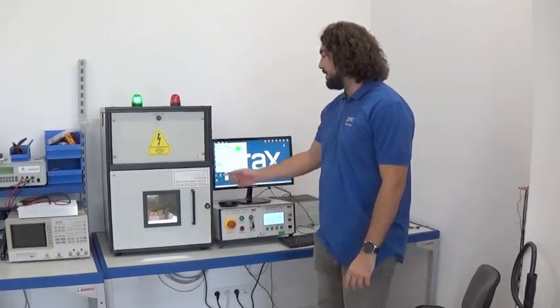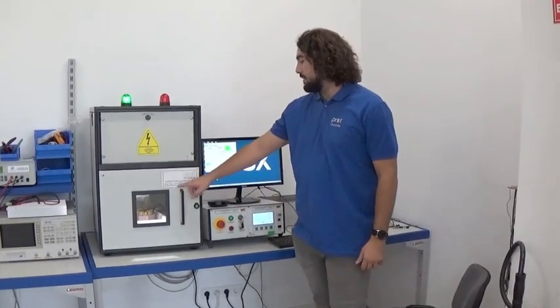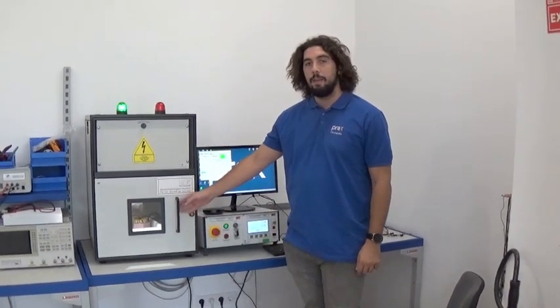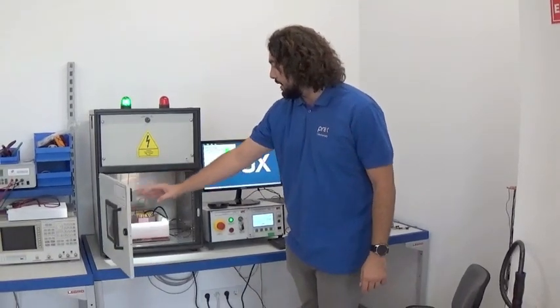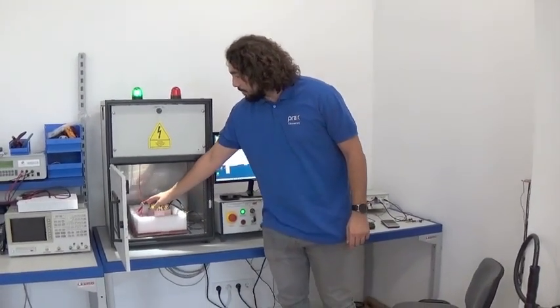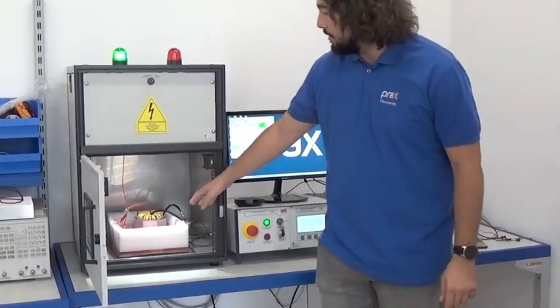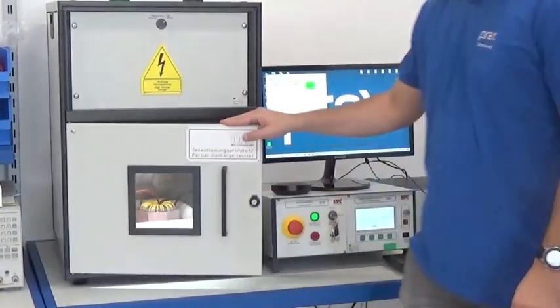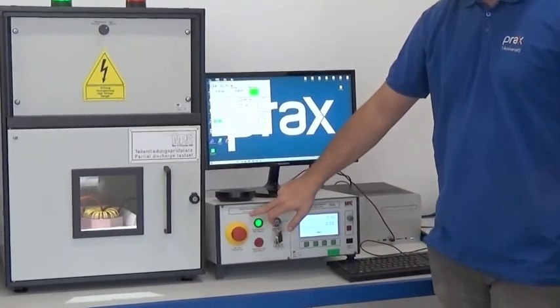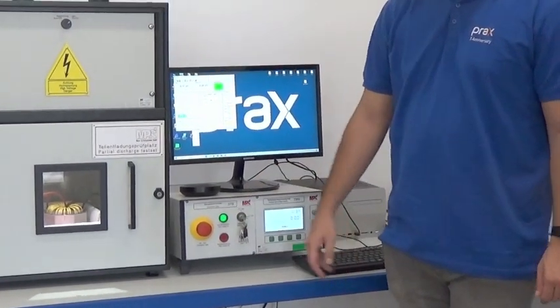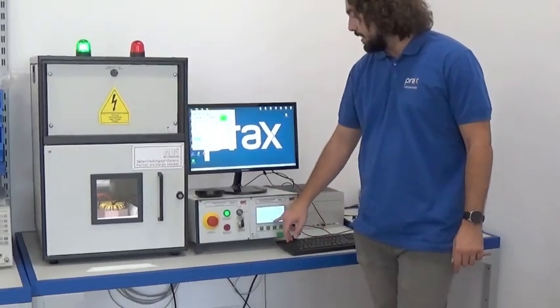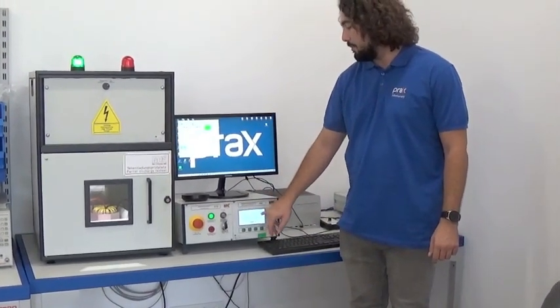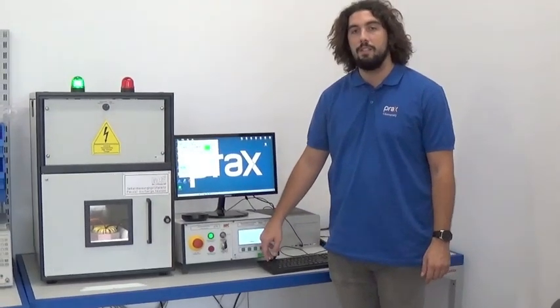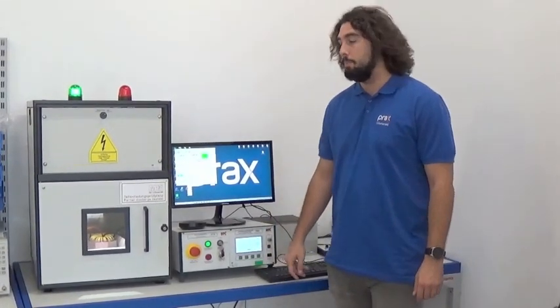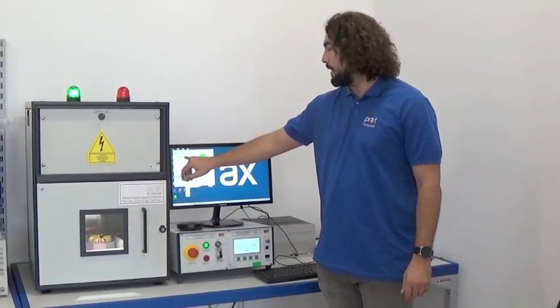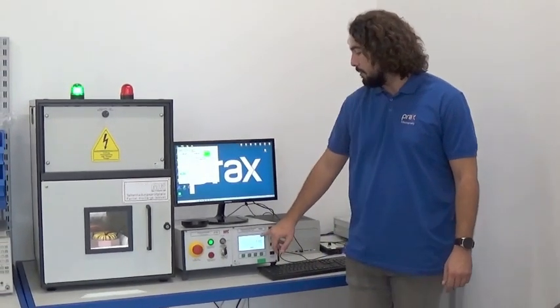So this is our partial discharge equipment. Here we have the partial discharge cabinet where we make the test. Here we place the parts, as you can see here. We connect the primary and the secondary side, separating it in order to make the test. Then here we have the control unit, which applies the voltage between the two isolated points, and here we have the partial discharge measurement, where we measure the partial discharge flowing through the two isolated points. And here we have the software where we can see the measurements that we are making now of the partial discharge.